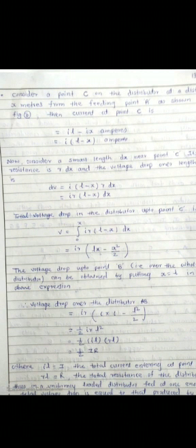Thus, in a uniformly loaded distributor fed at one end, the total voltage drop is equal to that produced by the whole of the load assumed to be concentrated at the middle point. Okay, so for a uniformly distributed load, the middle point should be assumed as the concentrated point.